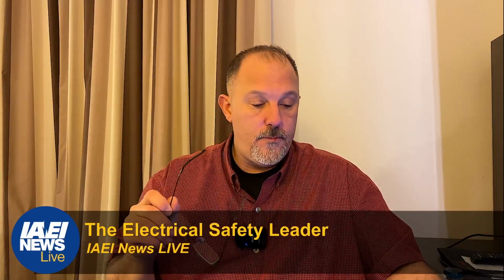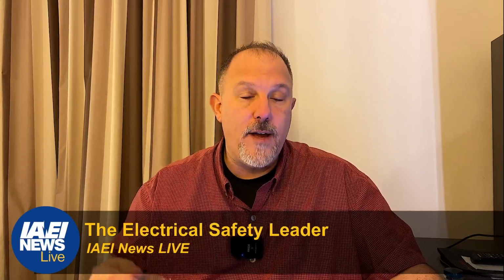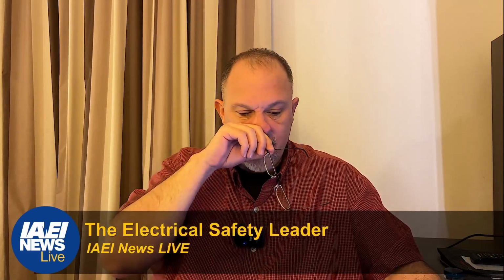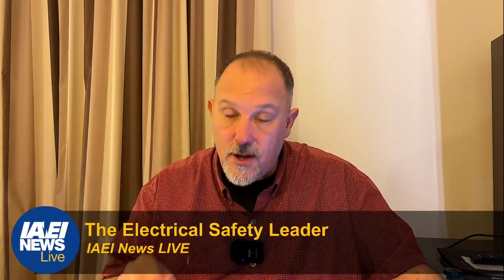Now, remember, when you have what we know as a duplex receptacle, there are two receptacles on a duplex receptacle. It's not a single receptacle. It's what the definition calls a multiple receptacle because you have two receptacles on the same yoke. You can get a single receptacle, but you can also get multiple receptacles on the same yoke, and that is multiple receptacles. It's not a single receptacle.